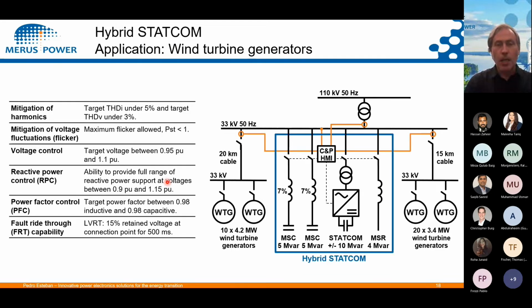I'll go to the next slide, because we have a part of the injection into the system that comes in real time from the STATCOM device, but then we have capacitor banks and shunt reactors that can provide extra inductive or capacitive reactive power to the installation, in a way that is cheaper, because it doesn't need to be produced by the STATCOM. Anyways, the capacitor banks and the reactors are controlled by the same control and protection system. Here are also some typical values again for harmonics, flicker (PST less than 1), voltage control, reactive power control, and fault ride-through, which is important in wind farm applications.